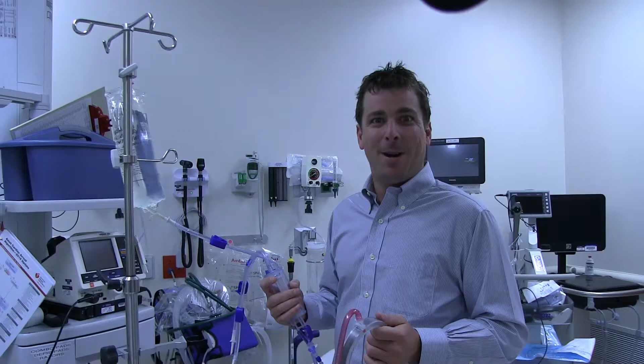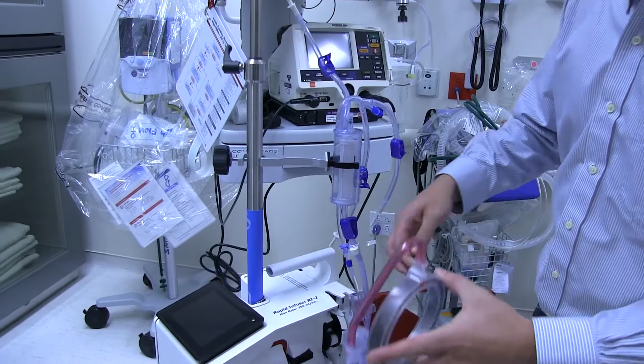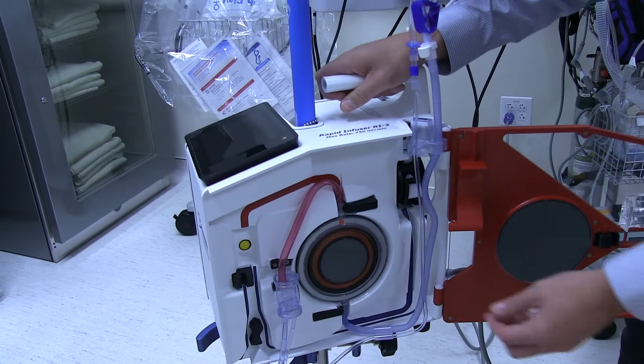You grab the tubing out of the kit, heater in your left hand, reservoir in your right. Pop the reservoir in first, then get this little red arrow pointing up and out on the heater next. You put those two pieces in first, then your hands are free and it's all color coded. Red to red. Instead of pushing this piece in, get the patient line pushed into the air detector, and that's going to hold that portion into place. Next, you get the blue arrow pointing in towards the machine to set this tubing into this air detector here.